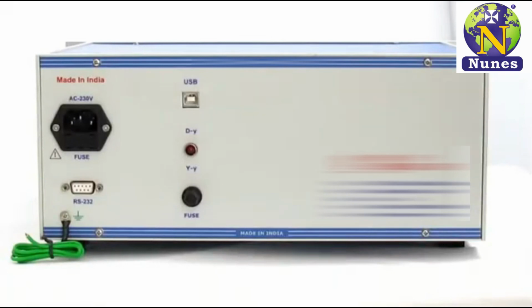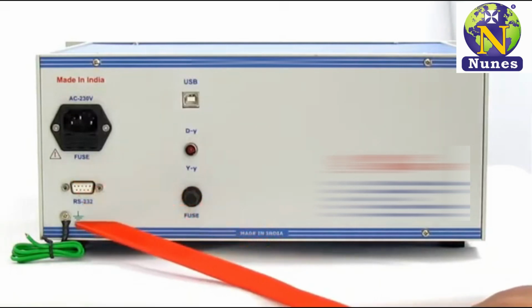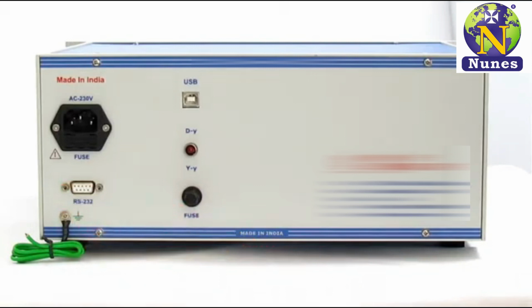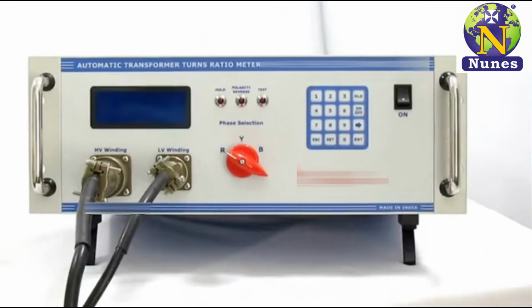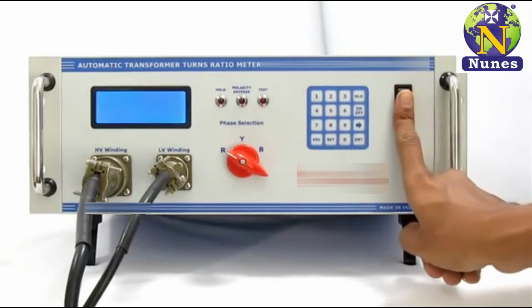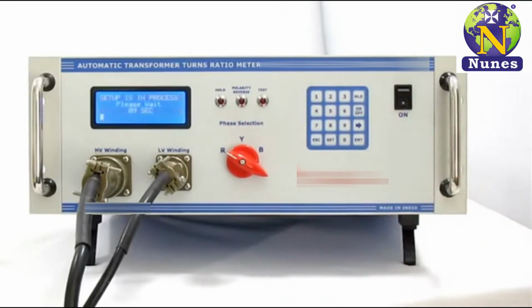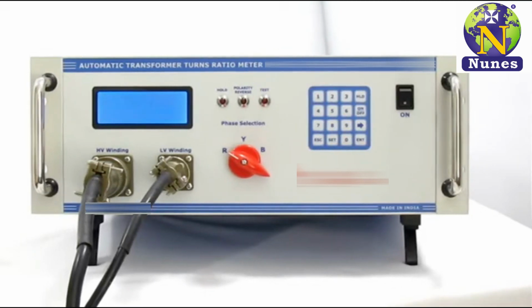Step 2. Ensure that TTRM is connected to proper earthing. So, connect your earthing terminal here to provide proper earthing to the instrument. Step 3. Now, turn on the instrument using the power on-off switch. Here you can see the instrument is on.